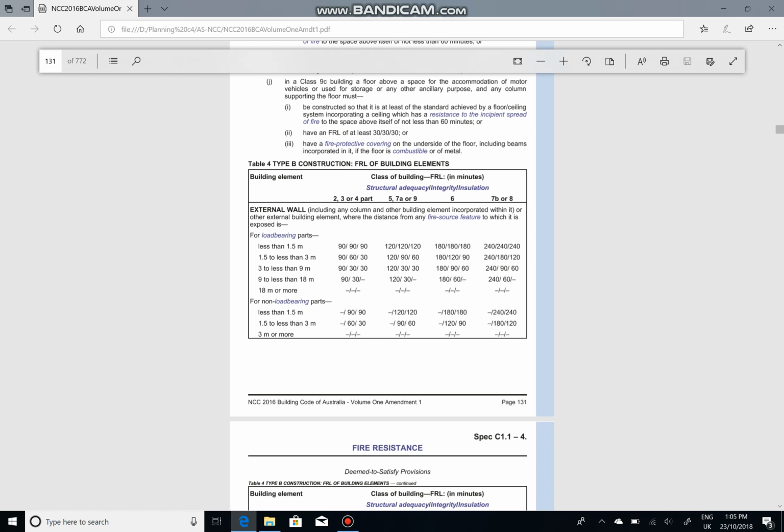So its integrity means there are no holes in the wall, so the wall can't be breached by fire. Fire can't make its way through a gap. And the final 90 or hour and a half is for insulation. So only a certain amount of heat from the side that's experiencing the fire is allowed to be transmitted to the side that is to be shielded. So it has to maintain its adequacy, its integrity, and its insulation for those 90 minutes.